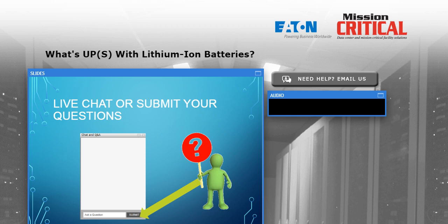What are the main safety preparations I should make on site before installation? You want to make sure that in your battery room you're not exceeding the total amount of lithium capacity in kilowatt hours as defined by the fire code. And again, like we mentioned before, I want to make sure I'm not mixing several different battery chemistries in one room, because the capacity limits would be reduced in that case.